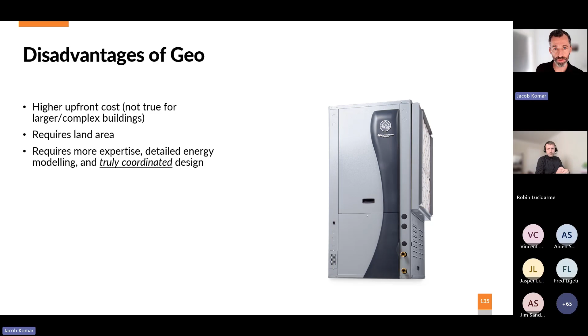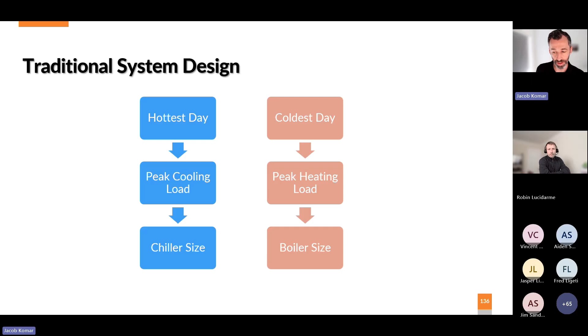Traditional system design is simple. You figure out your hottest day, you calculate your loads on the hottest day with all equipment, all lighting, everything maxed. You get your peak cooling load, and that's your chiller size. For the boiler, you assume there's no people in the building, no lights on, no nothing on your coldest day. That's your peak heating load, and that's your boiler size. As long as you keep paying your gas bill, you keep getting boilers. But the reality is that buildings don't operate that way. That peak load basically never happens.